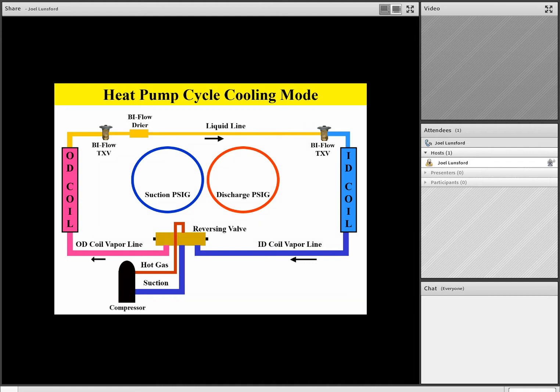The liquid will then pass down to a biflow TXV on the indoor coil, where it's going to be metering refrigerant into the indoor coil. Now remember, team, in the cooling mode of operation, the indoor coil is acting like an evaporator, and we have it color-coded blue, indicating it's cool or cold. From the indoor coil, we come down the indoor coil vapor line back to the reversing valve, where we loop through the reversing valve and to the suction of the compressor.